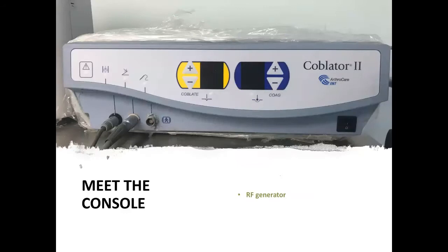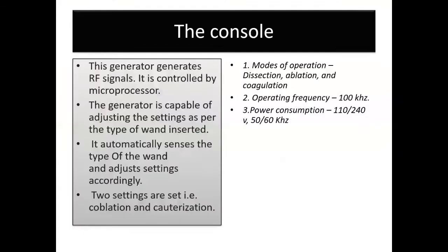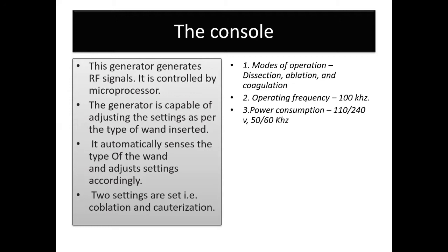The current generator is called the Coblator 2. The third generation was probably going to be released around the American Academy meeting but may be delayed. This is ultimately a radio frequency device with a microprocessor. The generator recognizes the wand inserted and automatically goes into the preset settings ideal for that particular wand. There are coblation and cauterization modes.